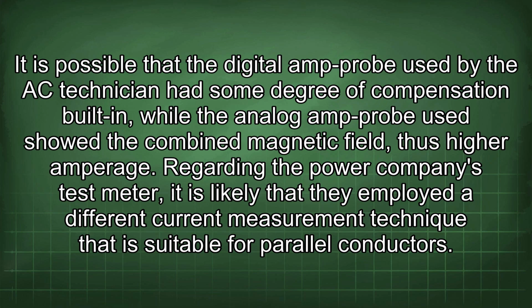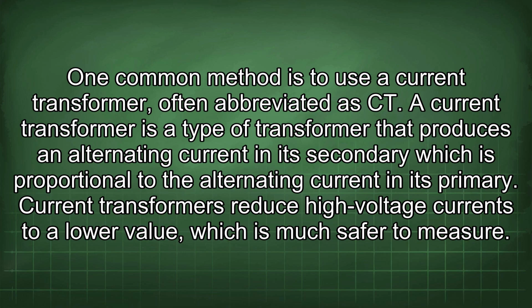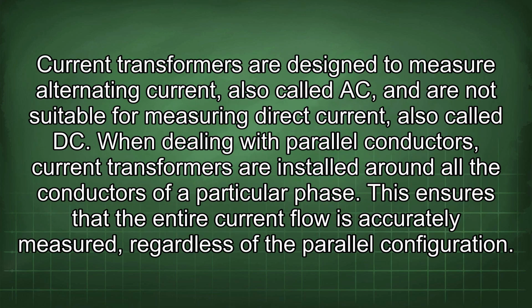Regarding the power company's test meter, it is likely that they employed a different current measurement technique that is suitable for parallel conductors. One common method is to use a current transformer, often abbreviated as CT. A current transformer is a type of transformer that produces an alternating current in its secondary which is proportional to the alternating current in its primary. Current transformers reduce high voltage currents to a lower value, which is much safer to measure. Current transformers are designed to measure alternating current, also called AC, and are not suitable for measuring direct current, also called DC. When dealing with parallel conductors, current transformers are installed around all the conductors of a particular phase. This ensures that the entire current flow is accurately measured, regardless of the parallel configuration.